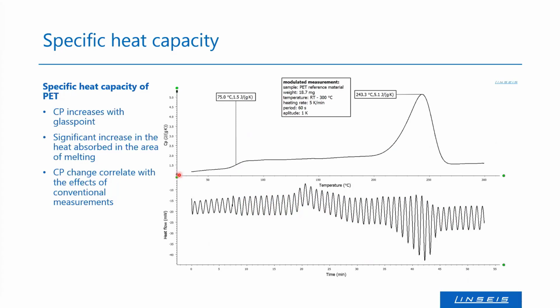So now let's come back to our PET measurement. Here you can find some more information about the measurement and a short evaluation. As I already mentioned, you can find the glass transition at 75 degrees, and the melting at roughly 243 degrees Celsius. The sample was a complete granule of 18.7 milligram, and I measured from 30 up to 300 degrees Celsius with a heating rate of 5 Kelvin per minute, a period of 60 seconds, and an amplitude of 1 Kelvin.